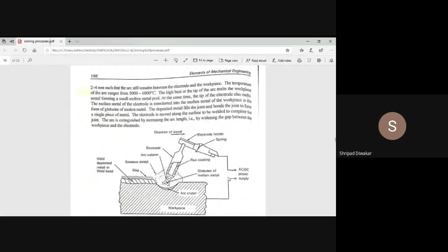Suppose I want to join two straight materials or square joints, in that case we have to maintain a gap of around 2 to 4 mm. Suppose you have no gap, in that case it is very difficult to pour the molten metal from the electrode into the workpiece. That's why it is always necessary to maintain a gap between the two workpieces, and it is called the welding gap. The welding gap usually varies from 2 to 4 mm.